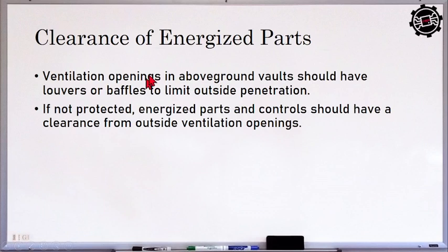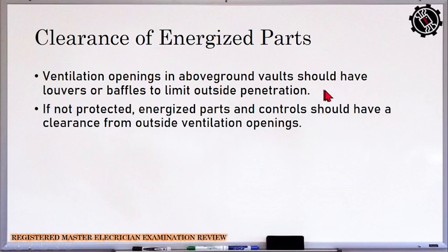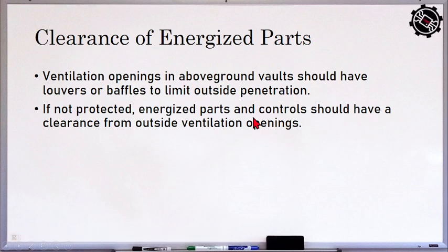Okay, so clearance of energized parts. So ventilation opening on above ground vaults should have louvers or baffles to limit outside penetration. So ibig sabihin, meron siyang louvers or baffles, na kung saan hindi pwedeng makapasok ang moisture or small drops of water doon sa ating equipment. If not protected, energized parts and controls should have clearance from outside ventilation of our underground supply system.